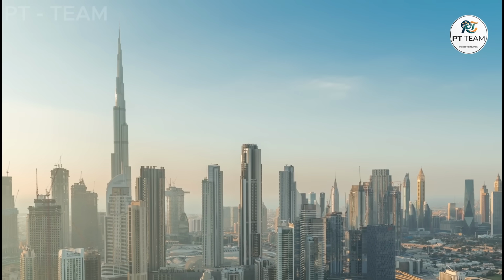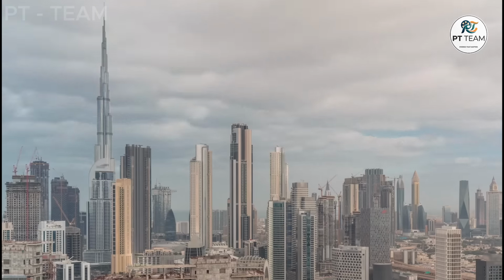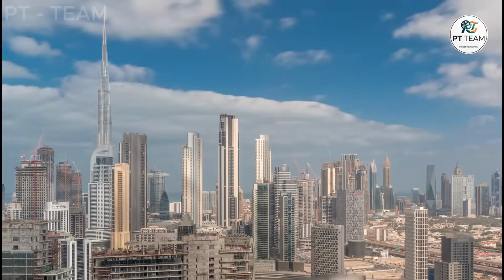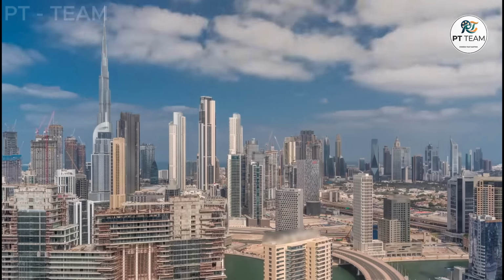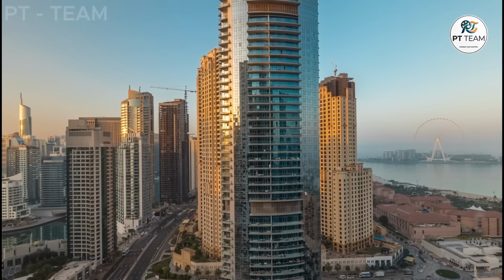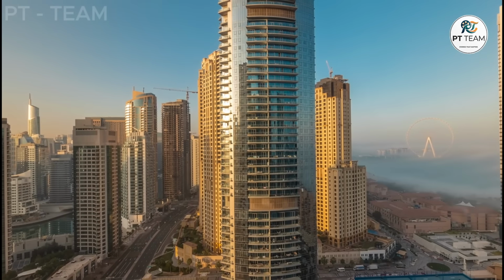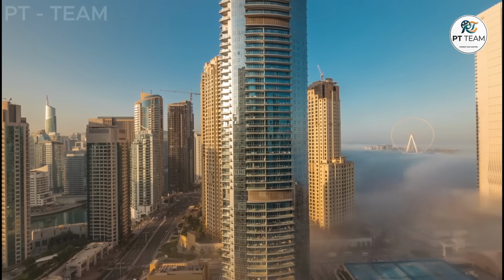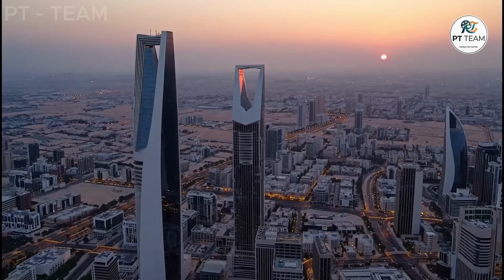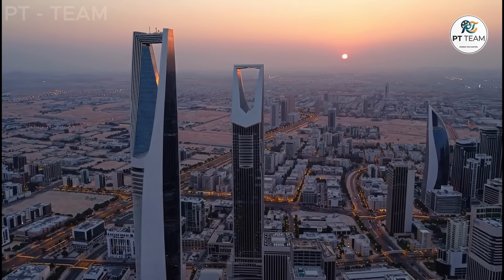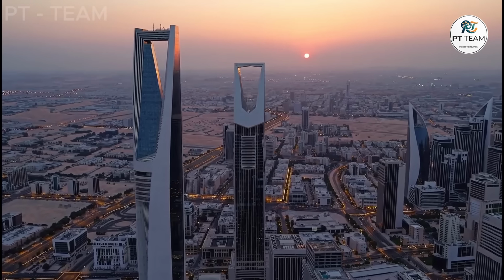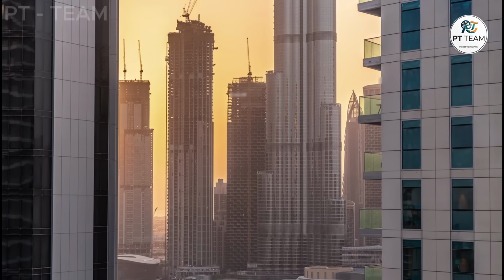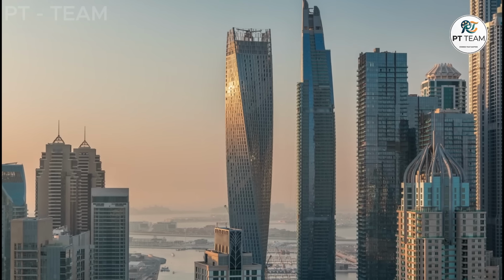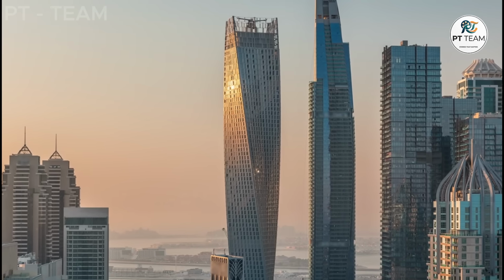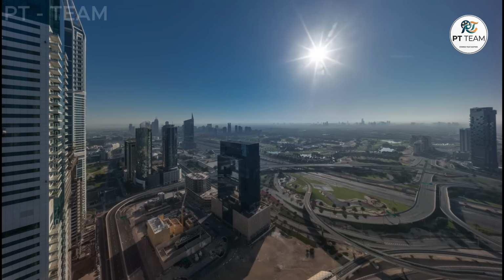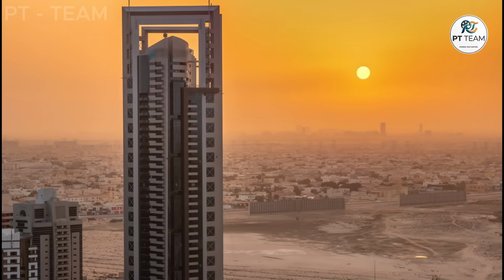Can a building actually be designed to be smarter than the dust storms that surround it? The industry is slowly shifting toward better technological solutions to manage this endless burden. Operators are increasingly installing advanced sensors to measure real-time pressure drops across multiple filtration stages. They are monitoring actual airflow volumes rather than simply checking if a fan motor is turned on. By placing particulate matter sensors both before and after the filter racks, engineers can detect bypass leaks before they ruin the cooling coils. Implementing predictive maintenance based on actual dust loading can optimize the replacement cycle and save significant labor costs. Some designs incorporate multiple stages of filtration to distribute the burden and extend the life of the most expensive media.